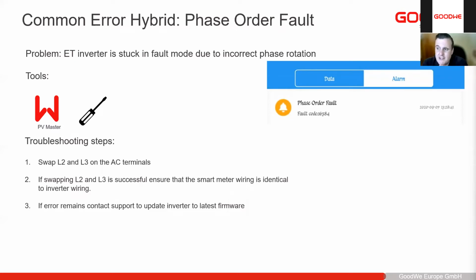But this does create a secondary problem with our smart meters. Normally you would install the inverter, the smart meter, everything the same. Now we have phase order fault. We rectify this at the inverter, but we've not rectified it on the smart meter, and that can lead to other problems. If we rectify this fault on the inverter, we need to swap it on the smart meter too, to make sure that the same phases on the inverter are the same phases on the smart meter voltage sense.